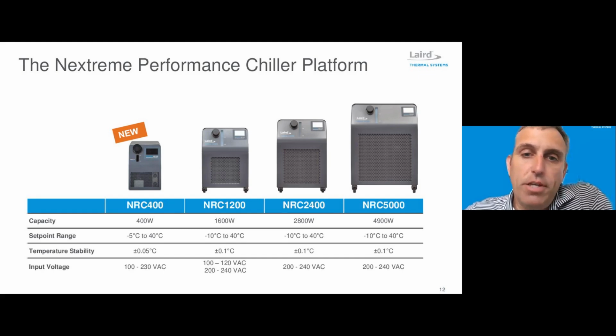The temperature stability is a fraction of a degree. So on the thermoelectric side, often with lower heat inputs and lower cooling capacities, it's easier to achieve higher temperature precision. So this is at 0.05. And then the refrigeration-based systems can achieve a 1/10 of a degree temperature stability.